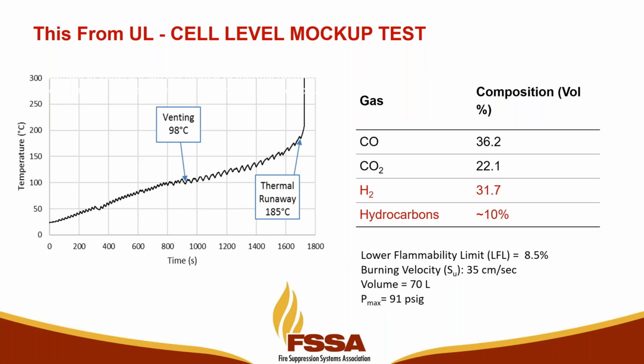But if we look at a unit level event, there's a lot of gas detection on the market out there, and I won't pick one in particular. I have a tendency to look at both hydrogen and CO, because if your hydrogen is not reading the way it should, CO can work as a precursor gas. Rising levels of CO and/or CO2 more likely indicate you've got some other things being released at the same time. So those are good options, but you really need to look at a building or unit level event beyond just off-gas. Off-gas is early warning detection.